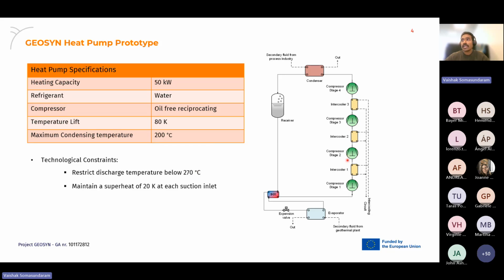In order to achieve that, we are providing intercooling between two stages of compression, and the compressor which we are developing has 4 stages, and we came to these 4 stages based on limiting the discharge temperature. In addition to that, in our basic configuration, we have an internal heat exchanger at the suction of the first stage in order to have the required superheat as well as to avoid any liquid compression at the first stage of the compressor.